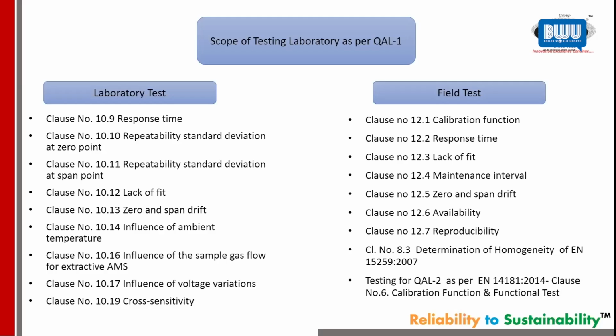And the field test, same thing. We have more added parts into that. It's calibration, response time, lack of fit, maintenance interval, zero and span drift. The most important here, you will see, is clause 8.3. I would like to highlight this, I'll take 2 minutes on that. Determination of homogeneity, EN 15259 is the standard. Now, the standard says, however big a certified equipment you have, whoever has done it, if it is not properly installed, it violates the certification clauses.